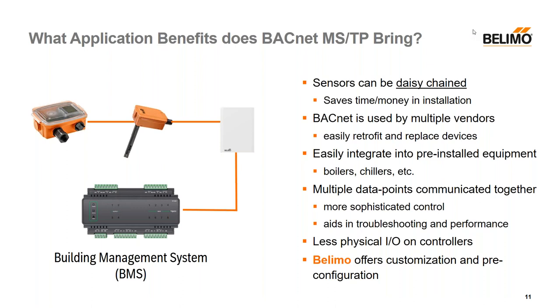Thank you DJ. As we close this webinar out, it's quite clear that there are many application benefits, both monetarily and in terms of time savings on installation — hardware, length of wire, amount of wire used, and the amount of physical controllers needed, especially when you're looking at different zones. Using a communication protocol like BACnet allows devices, specifically on the MSTP side, to be daisy chained together, which really helps save time and money specific to installation. It also decreases the amount of physical controllers needed, purely based on I/O count. BACnet is used by numerous vendors, which makes integration, retrofitting, device replacement, and device selection much more straightforward.